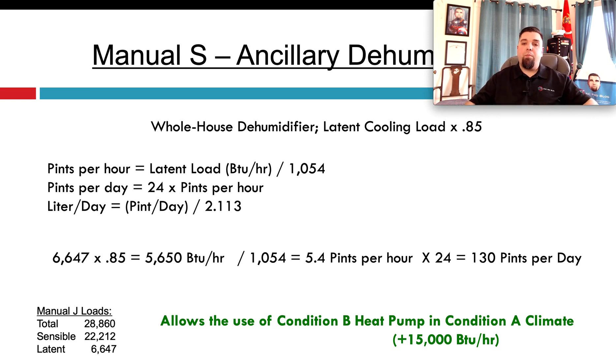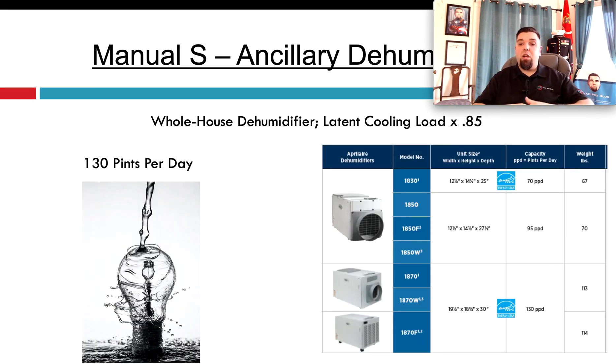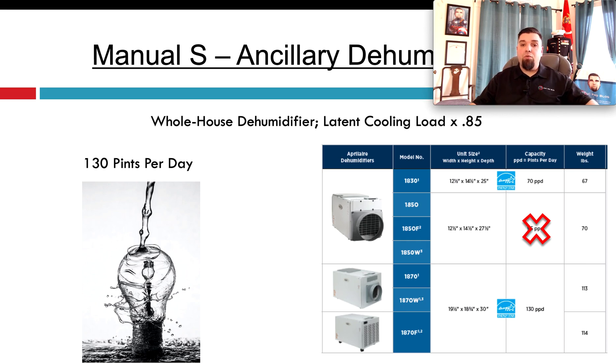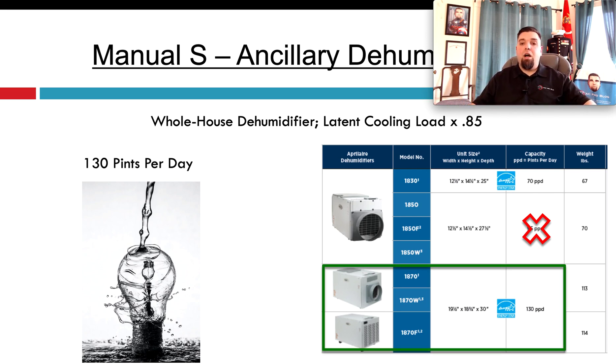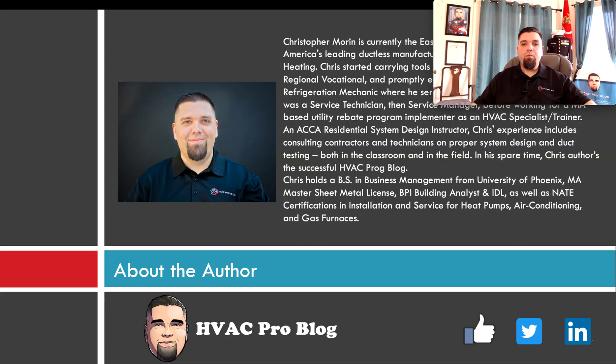In this example, I need 130 pints per day. Looking at the chart, I would not use the model that gives only 95 pints per day. I have the option of the bottom two or three models from this Aprilaire example — though it could be any manufacturer since they all rate in pints per day or liters per day. Those bottom models at 130 pints per day are what I would select.